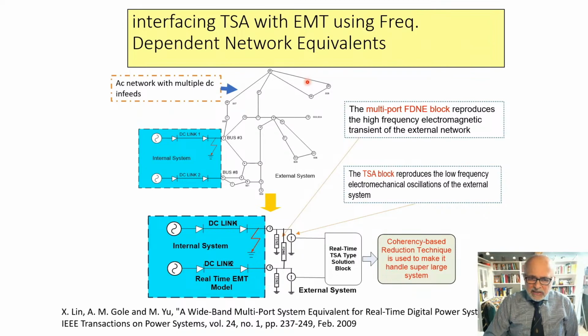So what can be done is there can be a certain combination of the two approaches, a hybrid approach used in the middle, whereas you put in the EMT program a frequency dependent network equivalent that represents the high frequency behavior of the external system, which is not modeled in the TSA program. And that is inserted into the EMT program here.